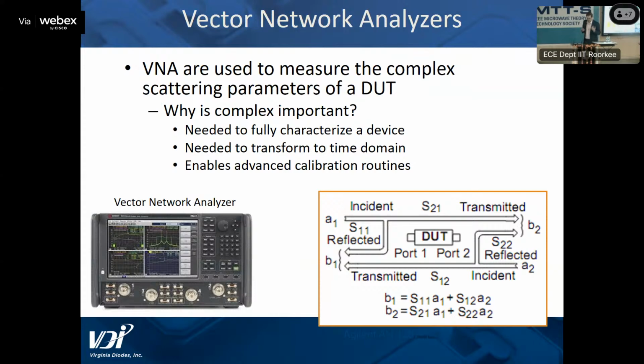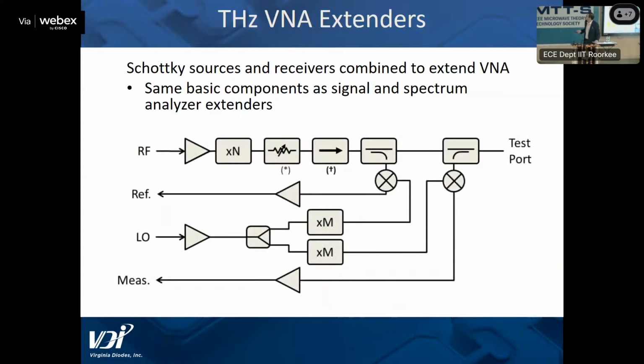You want to do that because you want all the information to fully characterize the device in both directions, amplitude and phase. You need all that if you want to transfer to the time domain, for example. And with a network analyzer, you have the ability to do very advanced calibrations. We can calibrate all the way up to the device under test. So inside the network analyzer extender, we have all those building blocks I spoke of.